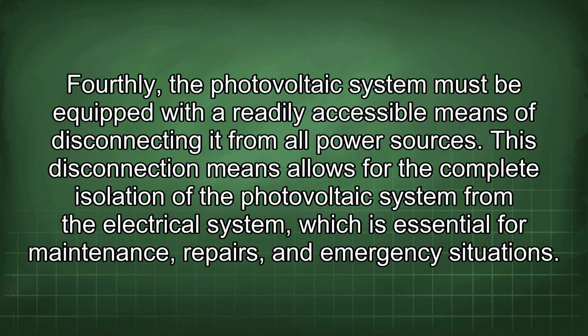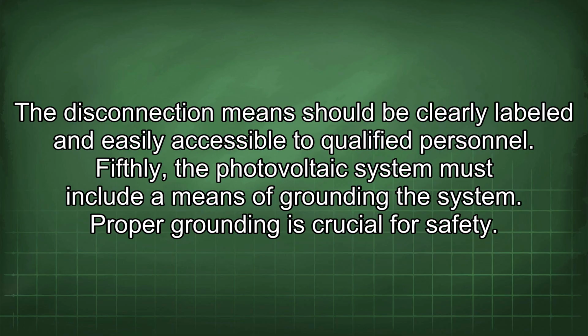Fourthly, the photovoltaic system must be equipped with a readily accessible means of disconnecting it from all power sources. This disconnection means allows for the complete isolation of the photovoltaic system from the electrical system, which is essential for maintenance, repairs, and emergency situations. The disconnection means should be clearly labeled and easily accessible to qualified personnel.